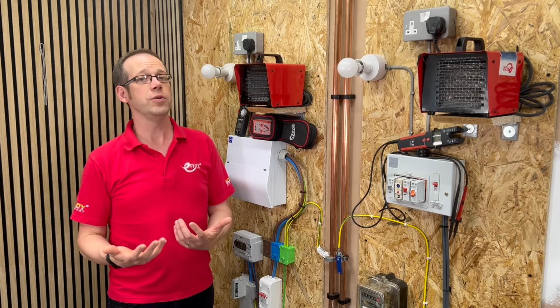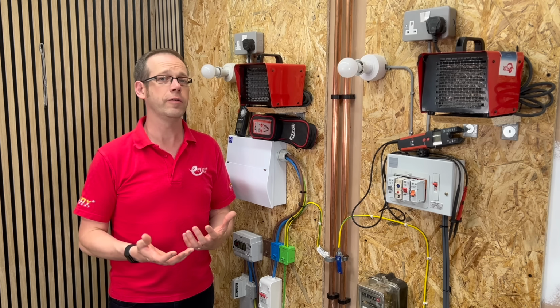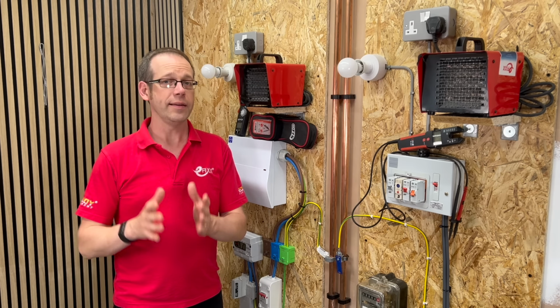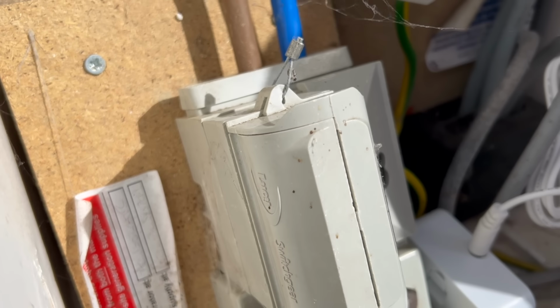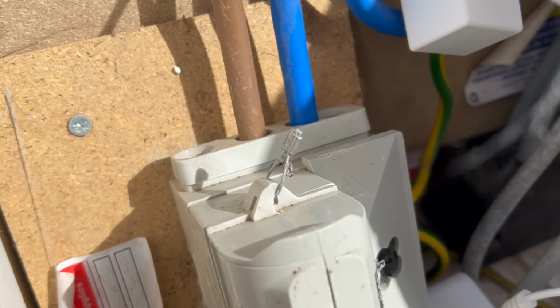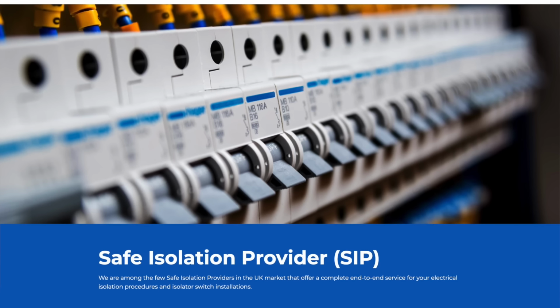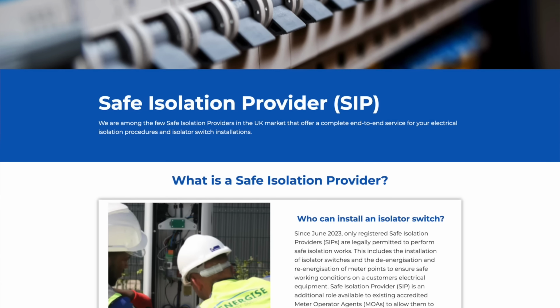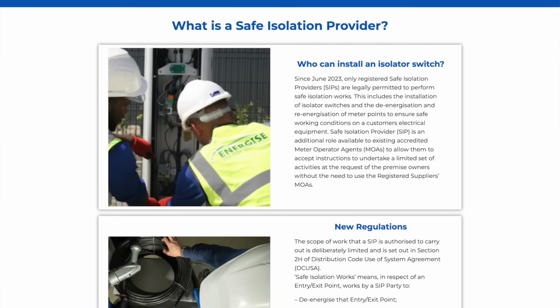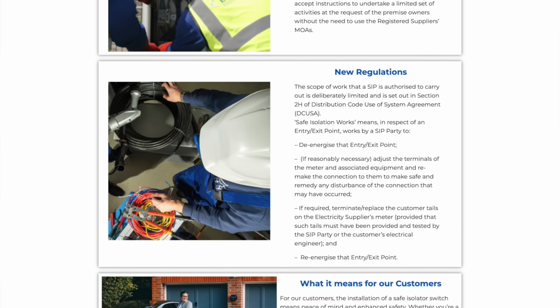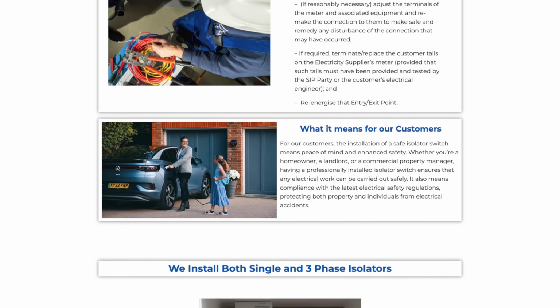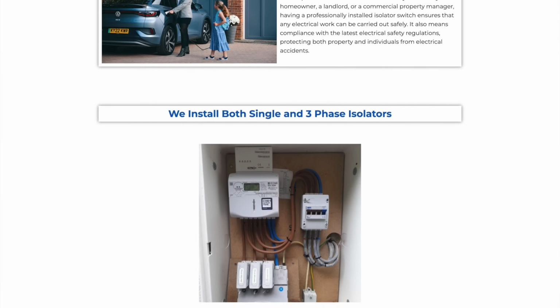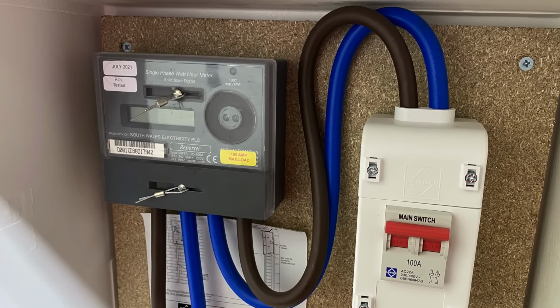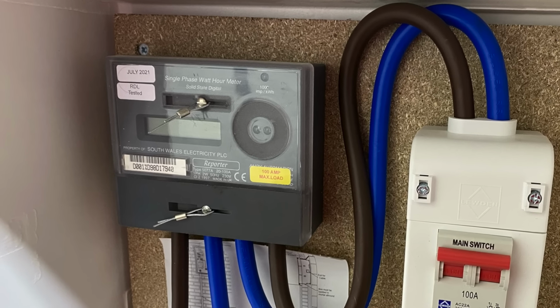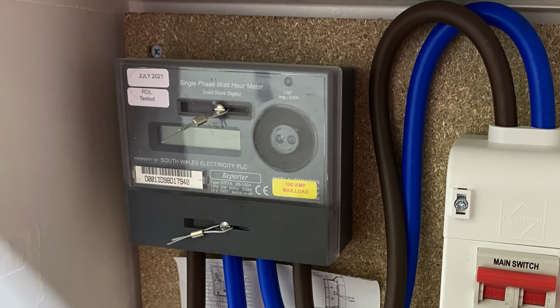And this is where confusion and misinformation often take over. To be absolutely clear, only the DSO, the energy supplier, or a licensed safe isolation provider, or SIP, can legally remove this seal and isolate the supply. A SIP is an authorised third-party provider who carries out safe disconnection of supply equipment on behalf of the DSO or energy supplier. While some DSOs offer schemes that allow electricians to perform certain types of isolation work, it's important to understand that these schemes do not permit the removal of seals on electricity meters. That responsibility remains strictly with the DSO or the supplier.